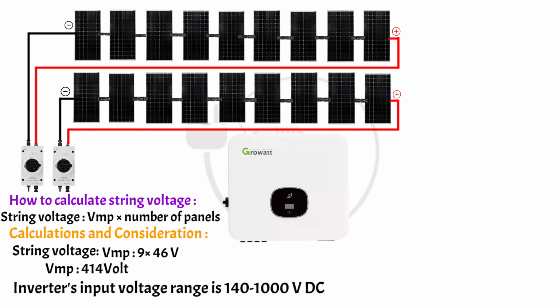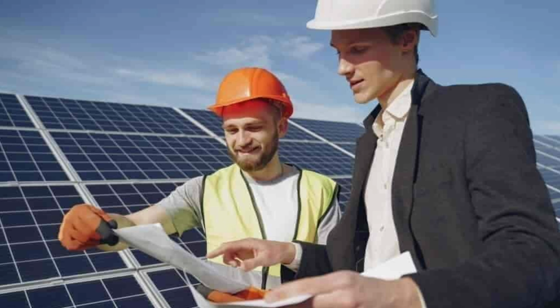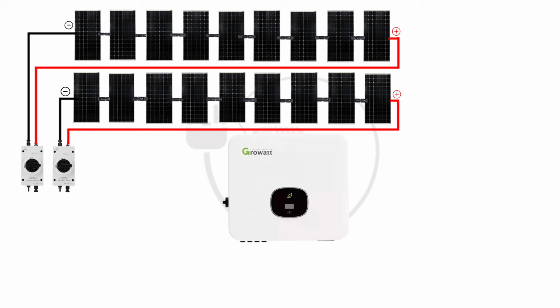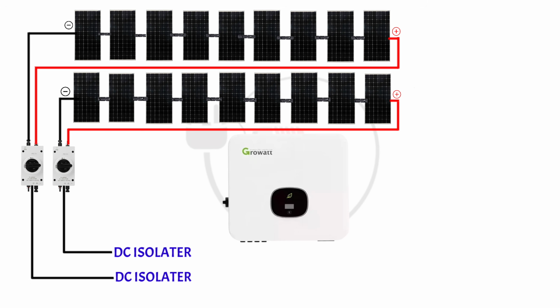The string voltage is within the inverter's operating range, and use the 2 MPPT trackers to ensure efficient power conversion. Professional guidance: it is highly recommended to consult a qualified solar installer. DC isolator. A DC isolator is a disconnect switch for a solar string. It is a safety device that allows you to manually disconnect the solar panels from the rest of the system.